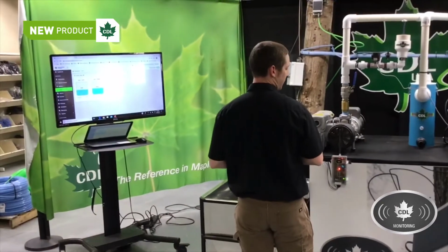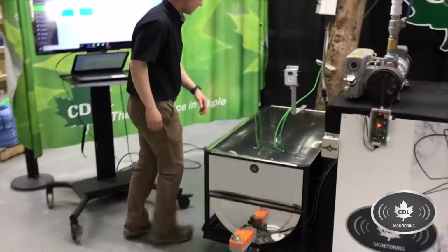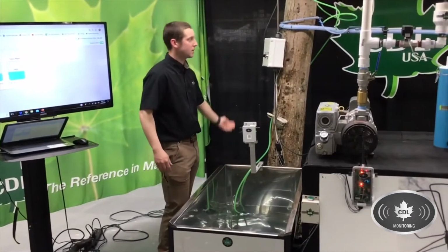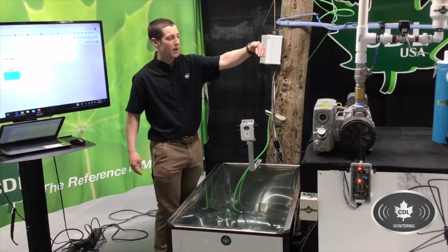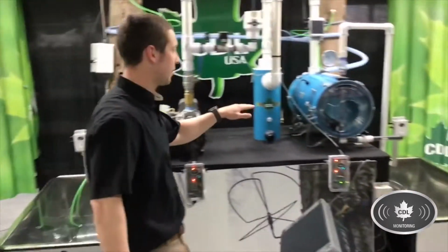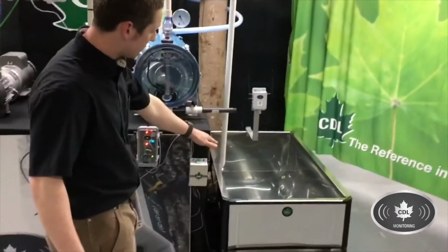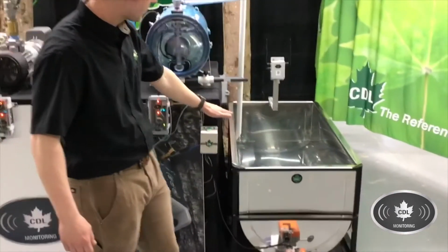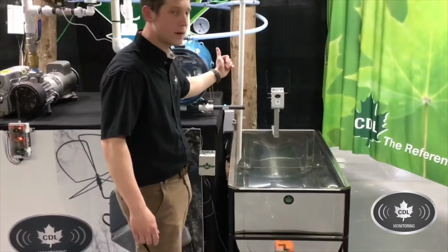What I'll do first is I'll go over what I'm going to do. So right here we've got a 5/16 into this tank. It's going to suck water through the main line using that vacuum pump. It's going to go into the releaser here. When it trips, what we're going to do with the automation is set it so that when the tank sensor reads a certain percentage, whatever I set, these valves are going to automatically open up.